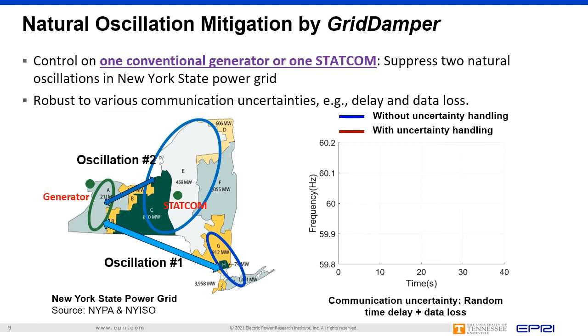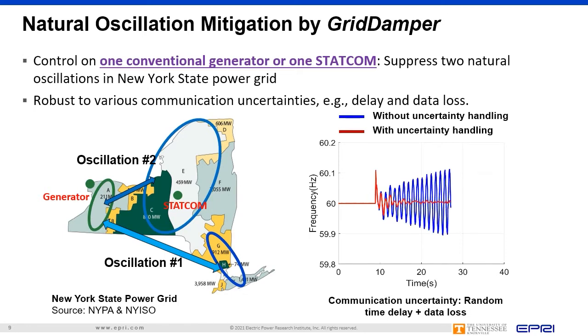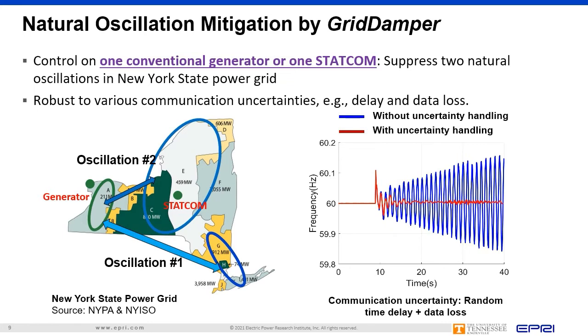Grid Damper is also able to deal with various types of communication uncertainties. The video on the right compares oscillation dynamics when the uncertainty handling function was activated versus deactivated. Without the uncertainty handling function, the oscillation was sustained and kept growing. When communication uncertainty handling was in service, the oscillation settled quickly within 20 seconds.